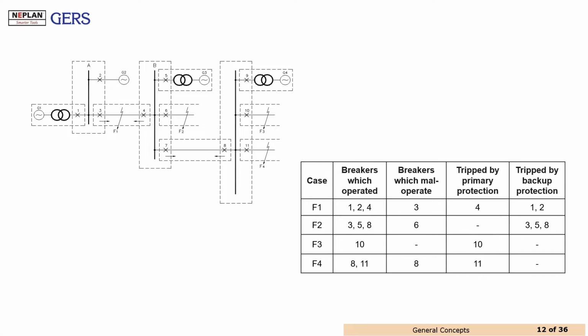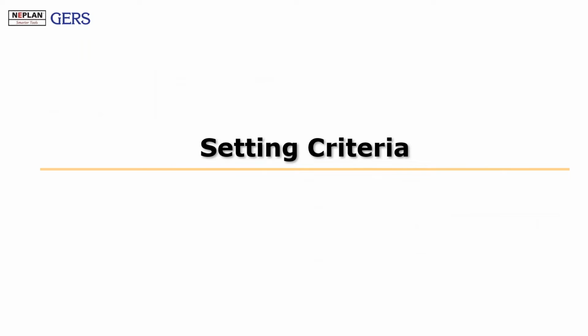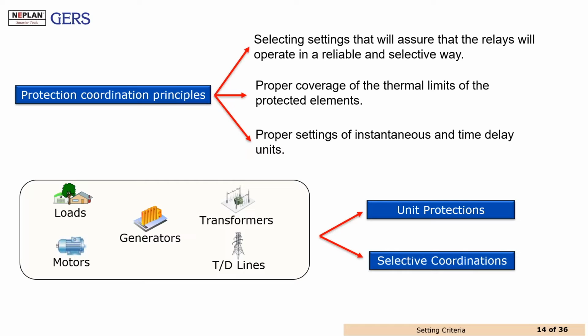These kinds of challenges are very common in protection scheme coordination. For that, we typically use power system analysis tools that allow us to set the selectivity of the network properly. For doing that, let me present some concepts about the setting criteria. The setting criteria are based on some protection coordination principles. The first one is the proper selection, in order to assure that the relays operate in a reliable and selective way.